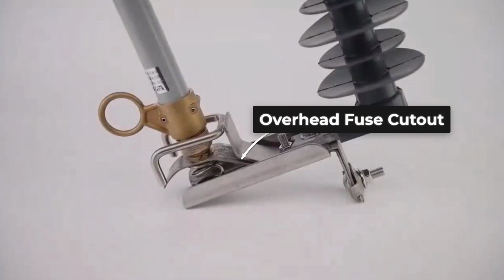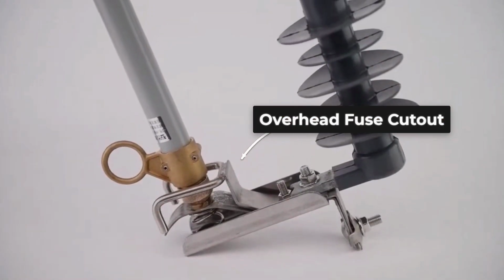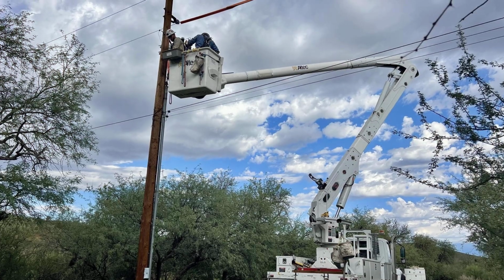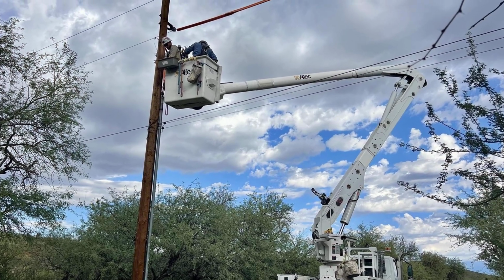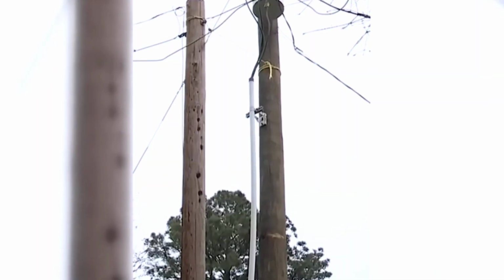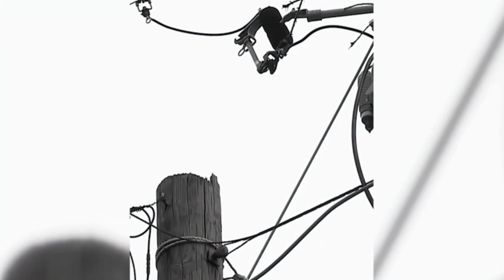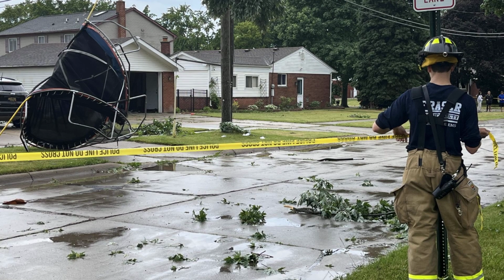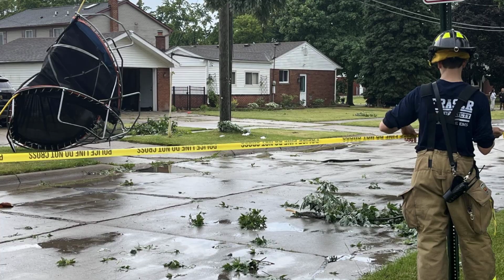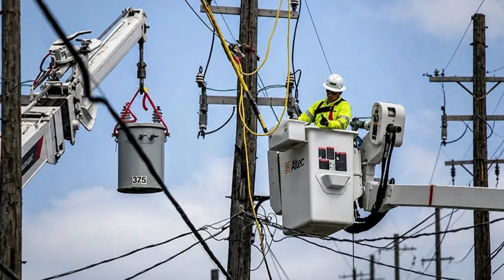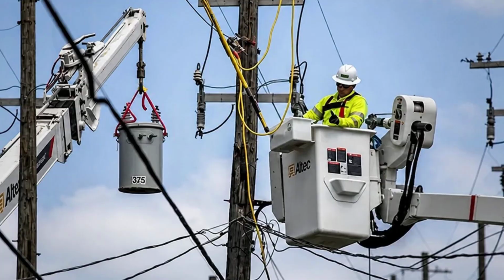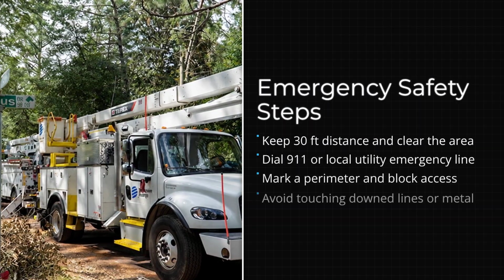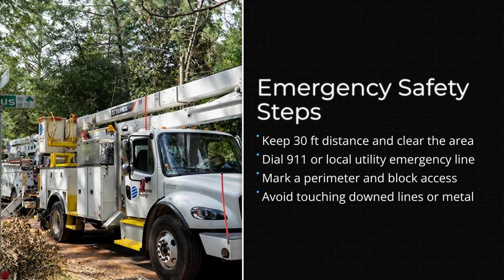It is actually the sound of protective hardware, like the overhead fuse cutout, opening instantly to disconnect the line and isolate the danger. While built to fail safely, any damaged utility pole or downed wire poses an immediate electrical hazard. If a transformer fails, the rule is simple: maintain a safe distance, keep everyone clear, and immediately call local emergency services or the utility company.